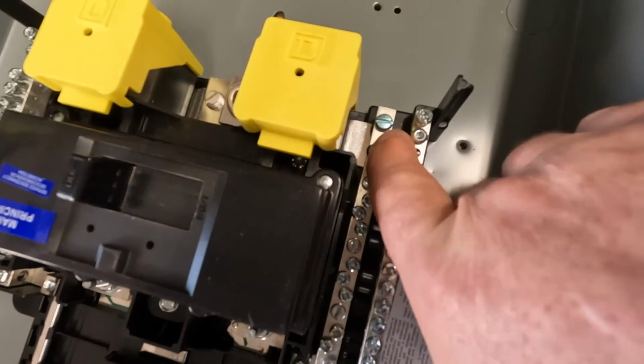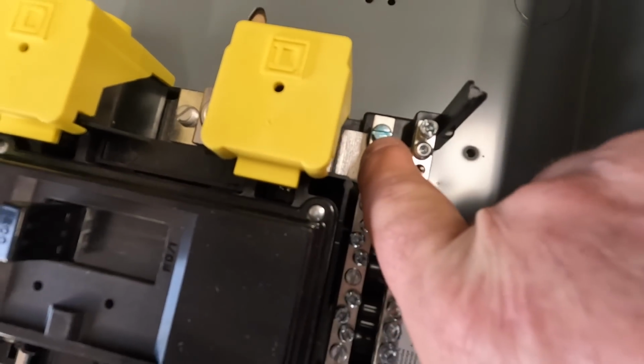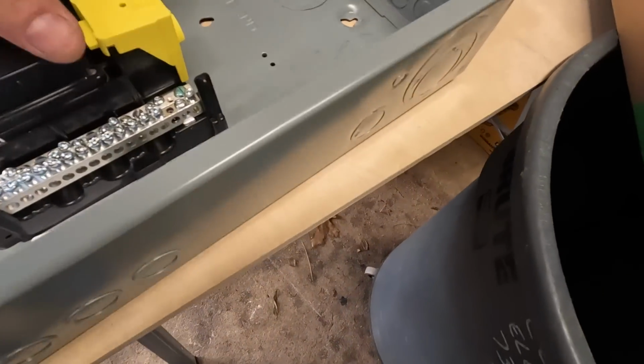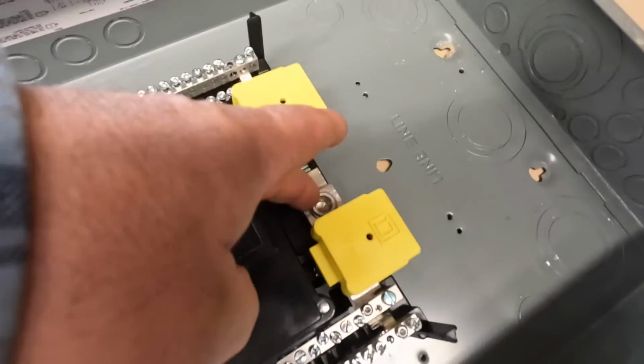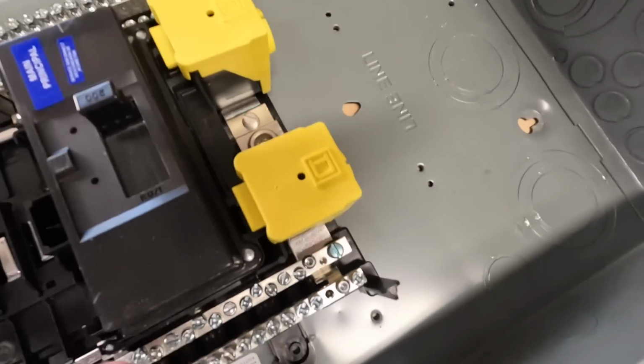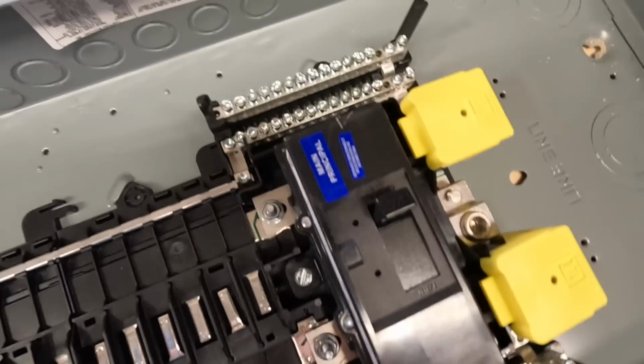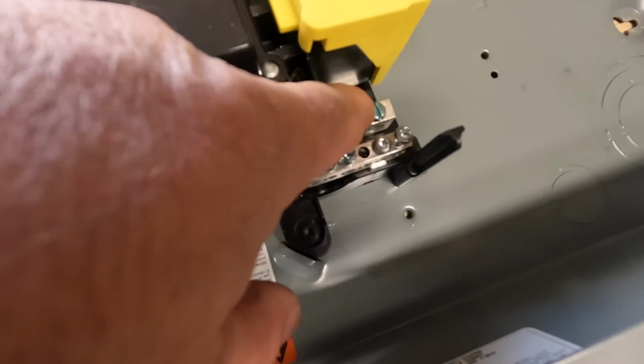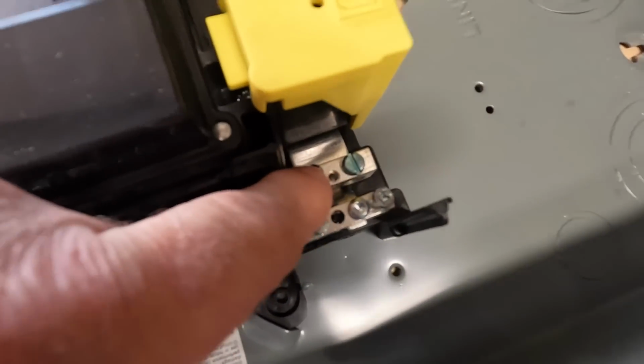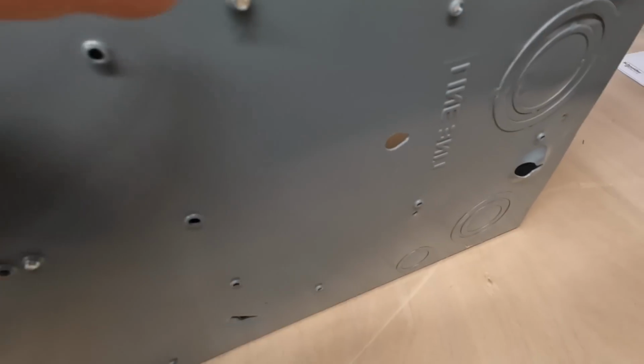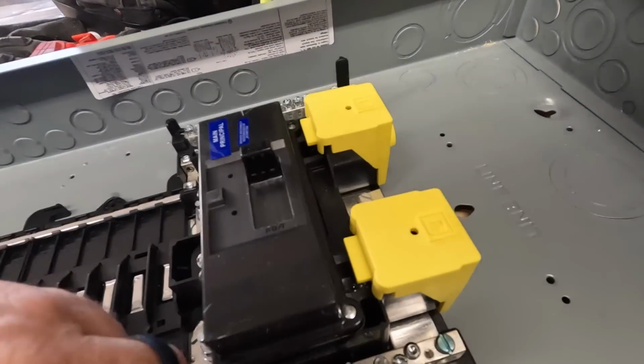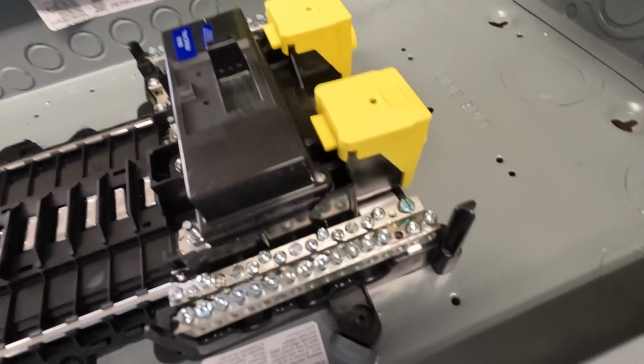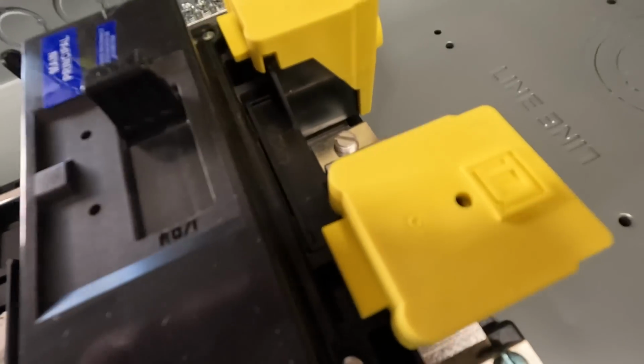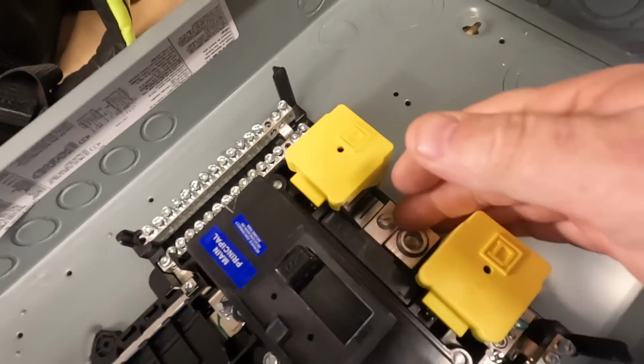And then of course I've already installed my main bonding jumper, and what this green screw does is it bonds the neutral. The neutral from the main lug right here, from the service neutral, is connected to these terminals on this side and on this side. When you put this green grounding screw in, or a bonding screw I should say, it engages the screw holes in the back here. And what that does is it bonds the neutral to the enclosure, forming everything inside here to be bonded with the system neutral.